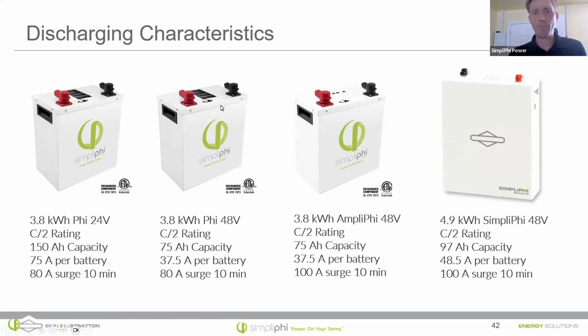On the discharge side of things, these batteries can actually surge, so you can get 80 amps out of the Phi battery, both varieties here, the 48 and the 24 volt, and that amperage is really limited on the 24 volt to that fuse and the BMS there. So again, 80 amps surge out of the Phi battery. You can get 100 amps out of the AmpliPHI battery. You can do that for up to 10 minutes.